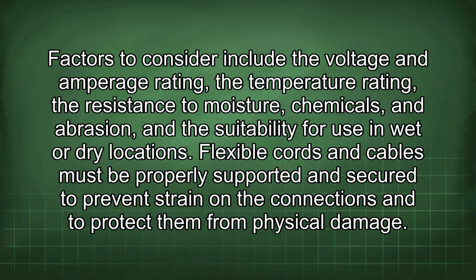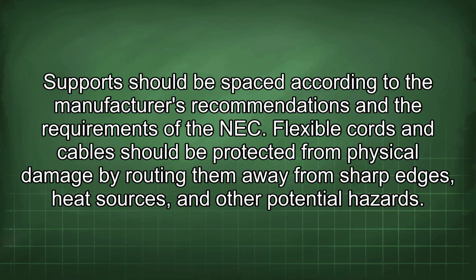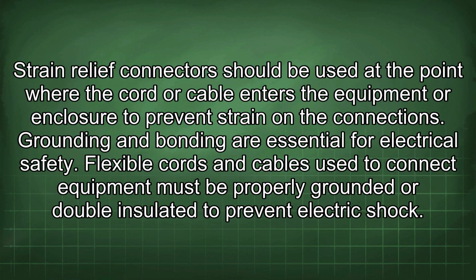Flexible cords and cables must be properly supported and secured to prevent strain on the connections and to protect them from physical damage. Support should be spaced according to the manufacturer's recommendations and the requirements of the NEC. Flexible cords and cables should be protected from physical damage by routing them away from sharp edges, heat sources, and other potential hazards. Strain relief connectors should be used at the point where the cord or cable enters the equipment or enclosure to prevent strain on the connections.